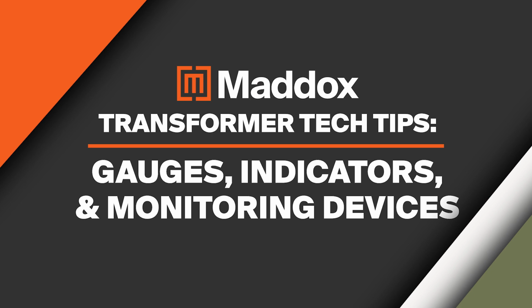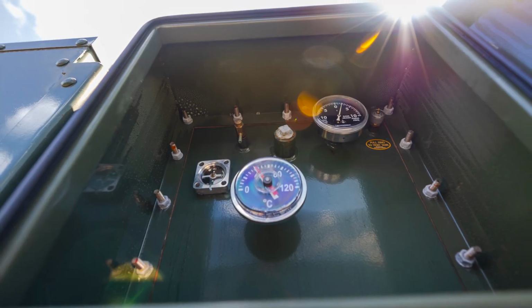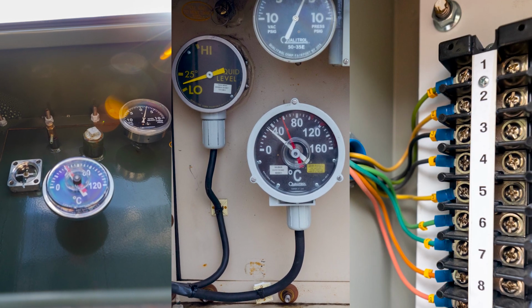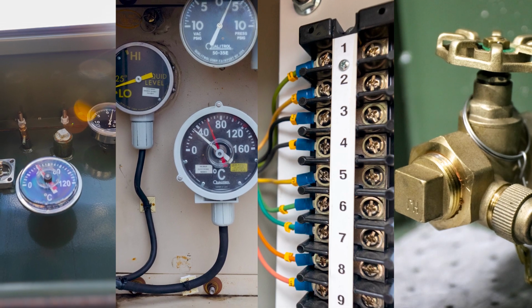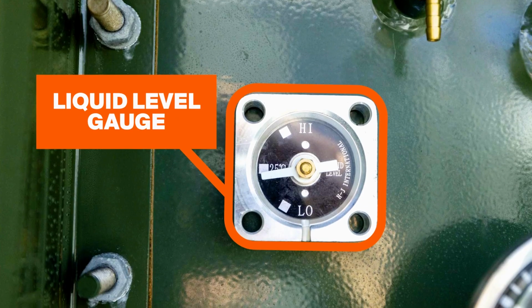Electrical transformers, much like cars or other machines, are outfitted with different gauges and indicators to ensure they're operating correctly under normal conditions. In this video, we'll look at common liquid-filled transformer gauges, alarm contacts and remote monitoring, and other valves and fittings your transformer may have. First, let's look at the liquid level gauge.